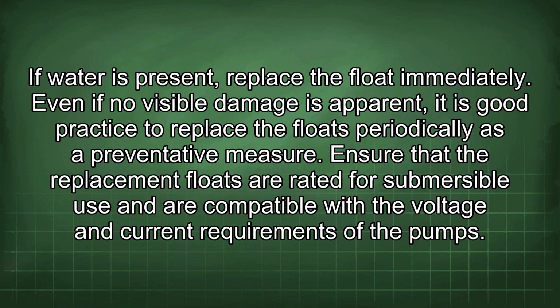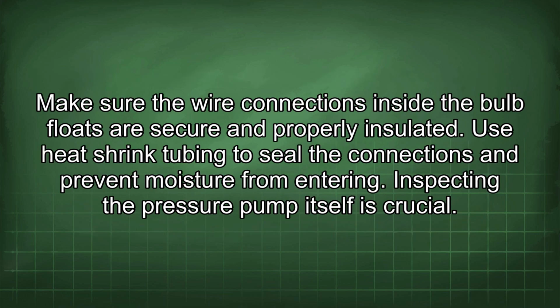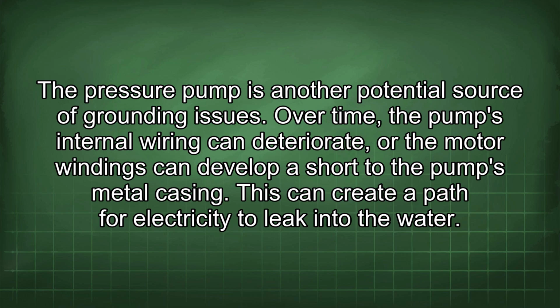Even if no visible damage is apparent, it is good practice to replace the floats periodically as a preventative measure. Ensure that the replacement floats are rated for submersible use and are compatible with the voltage and current requirements of the pumps. Make sure the wire connections inside the bulb floats are secure and properly insulated. Use heat shrink tubing to seal the connections and prevent moisture from entering. Inspecting the pressure pump itself is crucial. A pressure pump is another potential source of grounding issues. Over time, the pump's internal wiring can deteriorate, or the motor windings can develop a short to the pump's metal casing. This can create a path for electricity to leak into the water.